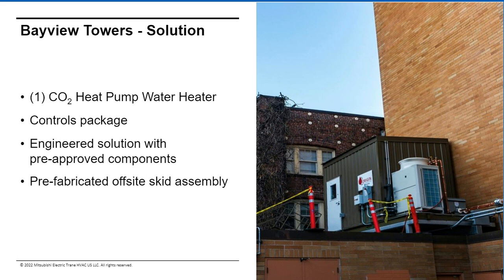So as you saw before, what we ended up doing for this project is leaving all the electric boilers or water heaters in place, and they act as that swing tank or regeneration for your recirc load. And then this is basically just our storage volume for the system. So even at 100 apartments, we can serve it with 1 heat pump in this scenario. And with this, we're doing a lot of extensive monitoring throughout the system to monitor COP, which has been very good, very high so far.